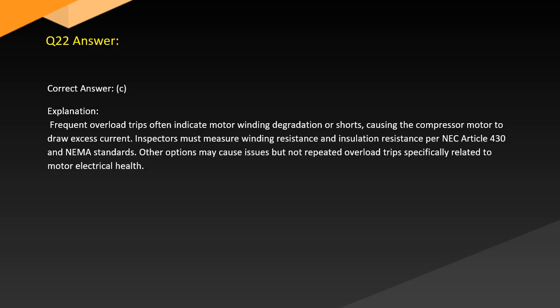Answer. Correct answer: C. Explanation. Frequent overload trips often indicate motor winding degradation or shorts, causing the compressor motor to draw excess current. Inspectors must measure winding resistance and insulation resistance per NEC Article 430 and NEMA standards. Other options may cause issues but not repeated overload trips specifically related to motor electrical health.